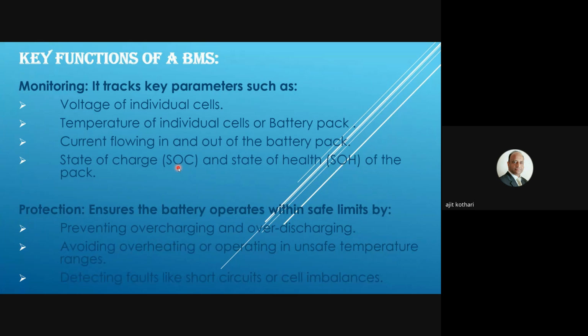State of charge is simple - it is how much charge is available in the battery bank. Now state of health is, let's say my battery bank has a capacity of 100 Ah. Instead of 100 Ah, after 2 or 3 years, I get 90 Ah. So the capacity after 2 years is now 90 Ah, and the state of health is 90 Ah. That is how we calculate the SOH, because if state of health is reducing, we call it degradation of the battery. So battery capacity cannot be 100% till its end of life.